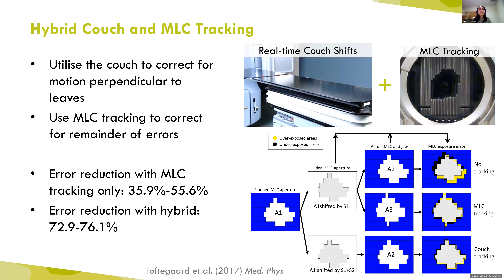in our target. So one of the ways we can address this is by combining it with real-time couch tracking. So this is where we actively move the couch during treatment to compensate for any of the motion that we're seeing in the patient. So we can use real-time couch tracking to correct for all of the motion that's occurring perpendicular to the MLC leaves, and this is helpful because the resolution at which the couch can be shifted is smaller than the width of an MLC leaf. And then we can use MLC tracking to then correct for the remaining errors that are occurring parallel to the MLC leaf direction. So this has been implemented experimentally. It has been shown that performing this hybrid strategy can reduce the tracking errors compared to using MLC tracking alone.